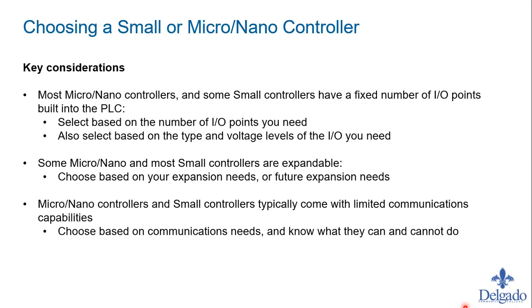Also make sure you're picking the right voltage levels. The micro/nano PLCs usually come a certain way — either 120 volt AC or all 24 volt DC — there's usually not a combination. So know your control voltages. Some are expandable, so choose based on your expansion needs, and look at what communications options those small controllers have available.